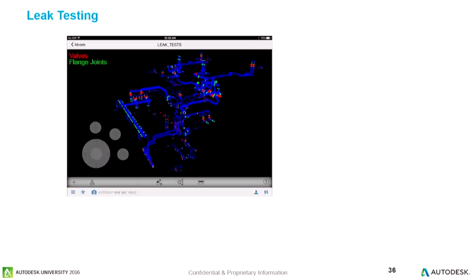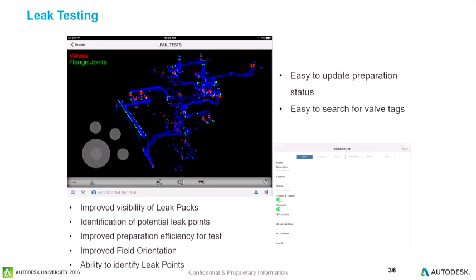We could also capture which were the leak points. In the first 3 leak tests we identified a problem with autoclave fittings. So we got ahead of time and checked all the other leak packs that had autoclave fittings, doing a double check to reduce the number of leaks we experienced later.